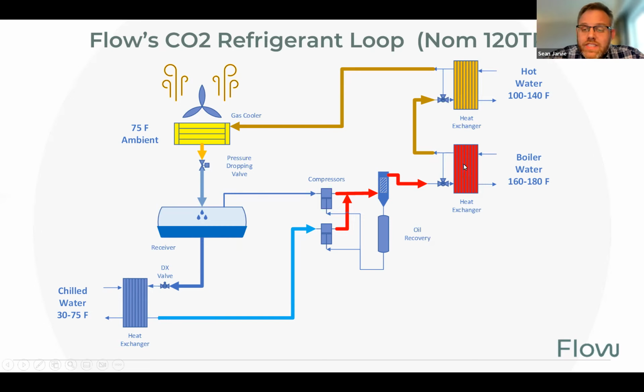Every one of our units is set up with up to 2 heat exchangers. Now we can do things like run our hot water boilers on one circuit, and maybe a domestic hot water or air handling hot water heaters or in-floor heat or whatever else you might want to do, thermal energy storage. The possibilities with a system like this are truly amazing. And each one of these systems can be turned down to 0% modulation. So you can actually turn an individual set point and circuit off inside of the unit.